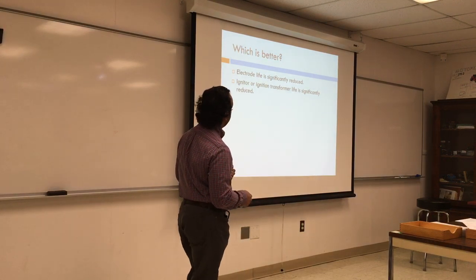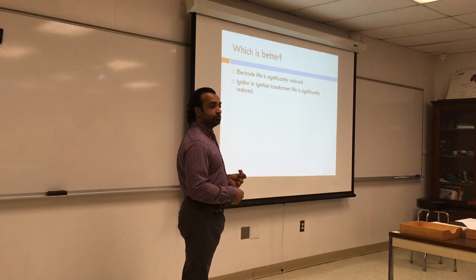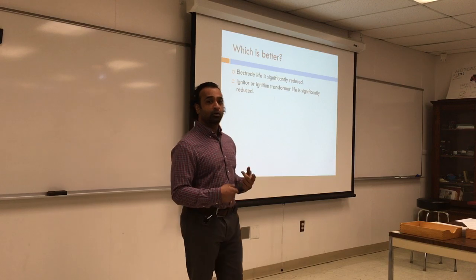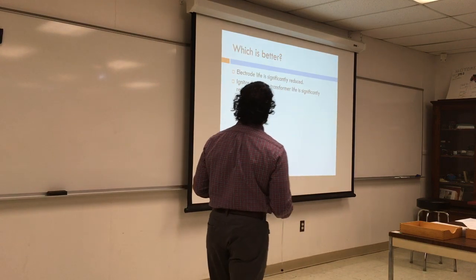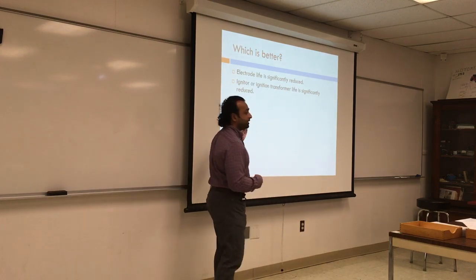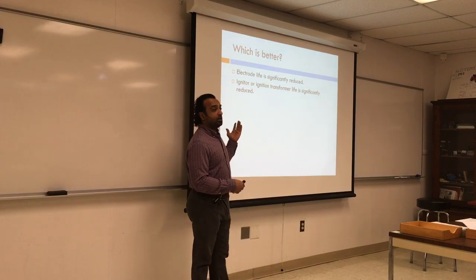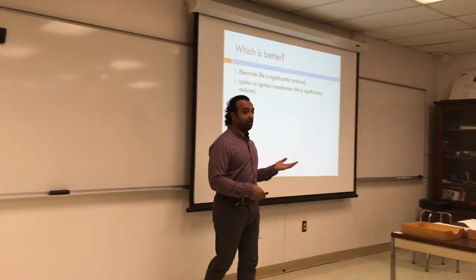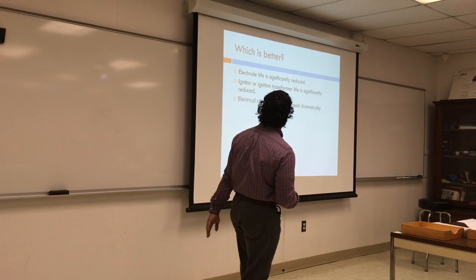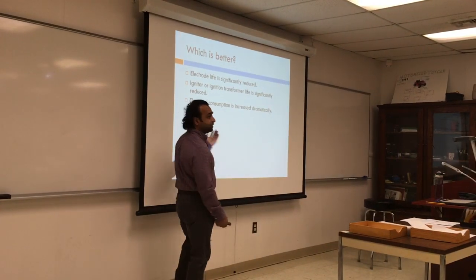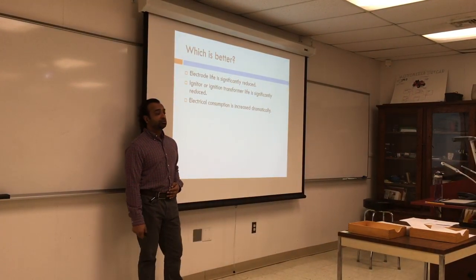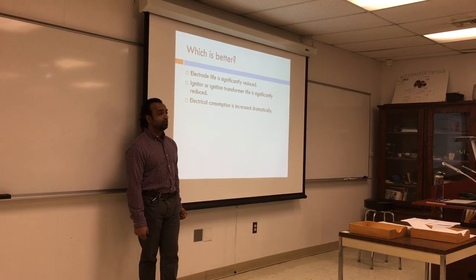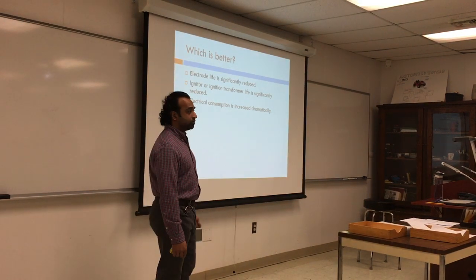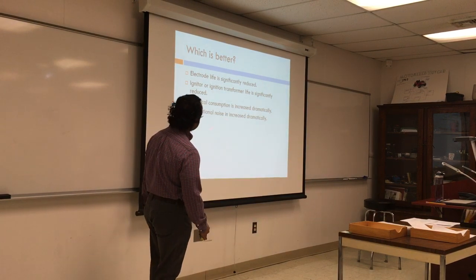The igniter, the ignition transformer life is significantly reduced because you're keeping it on all the time. It's not good to have it on all the time. And also, if it's on, it's going to consume more power, right? So power consumption of a transformer is around 150 watts. That's a lot of money. If you keep that on for 12 hours a day, that will cost you a lot of money.